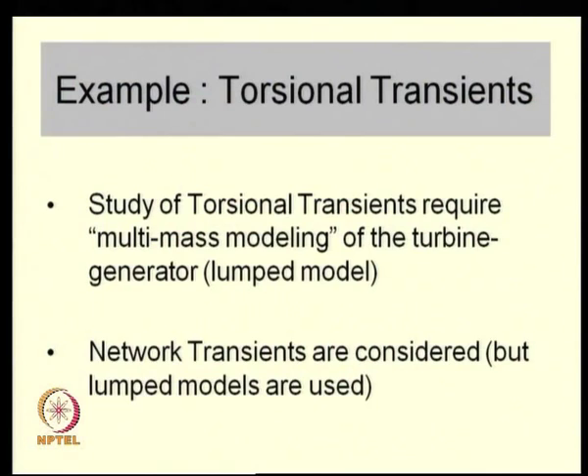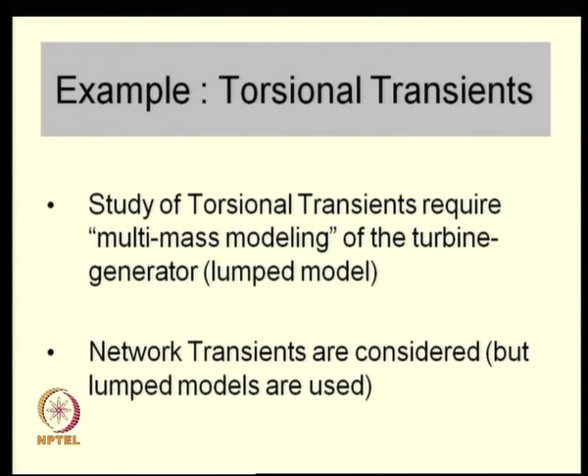That is the last part of the course on stability improvement. Just to recap, torsional transients require multi-mass modeling. Whenever we are studying torsional transients, the speed of all the turbines and the generator is not the same. Though in steady state they are the same, the transient differences in speed are usually caused by torsional oscillations.